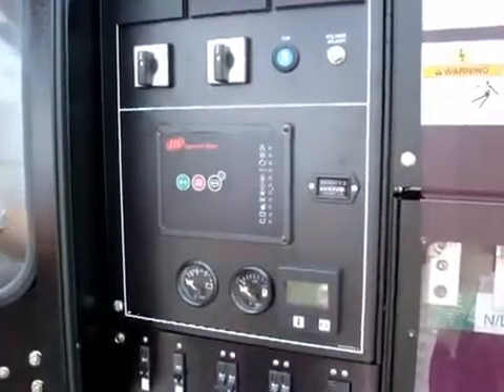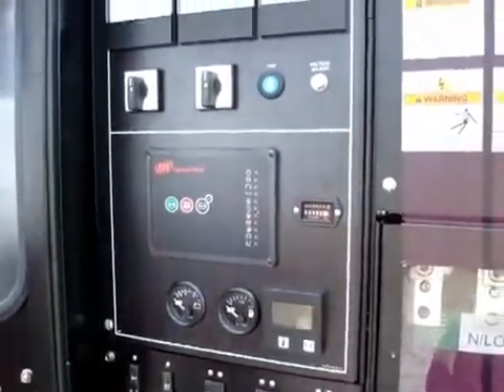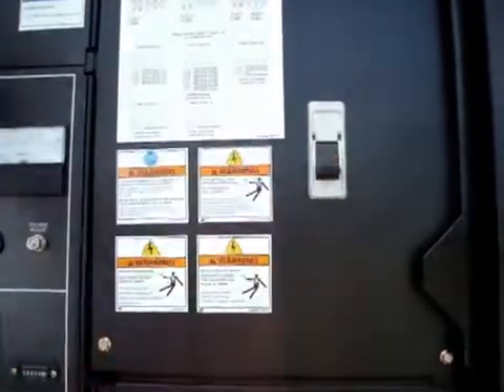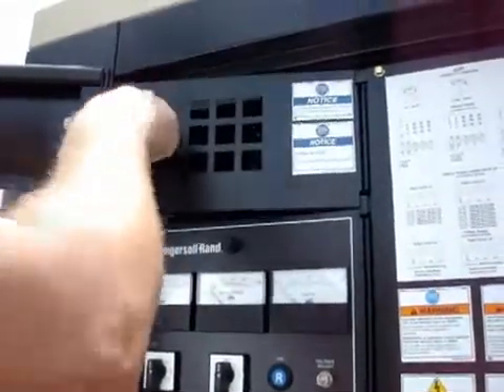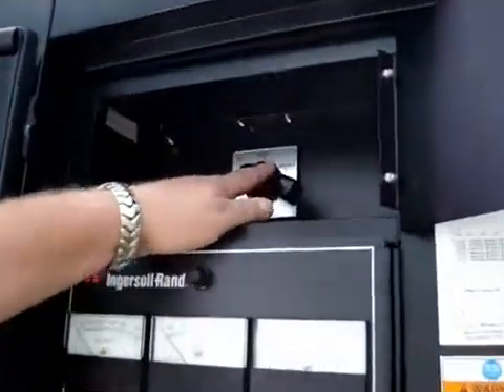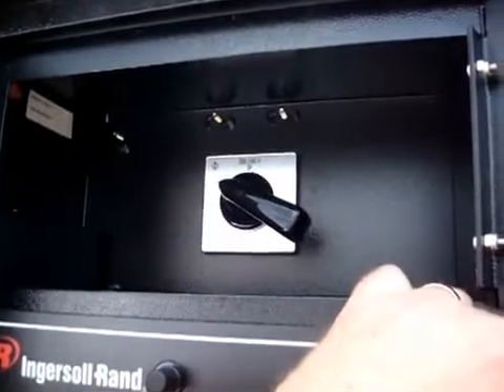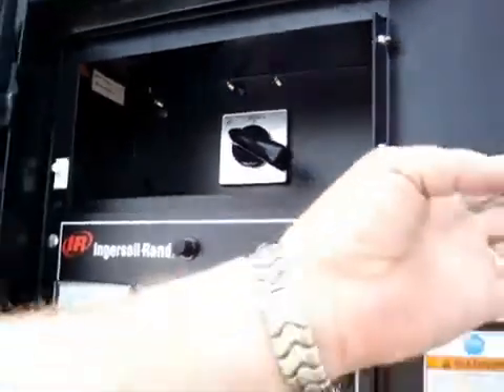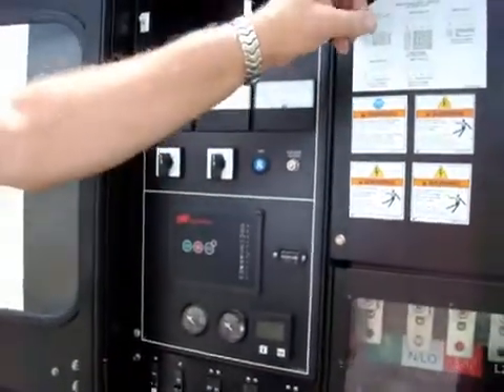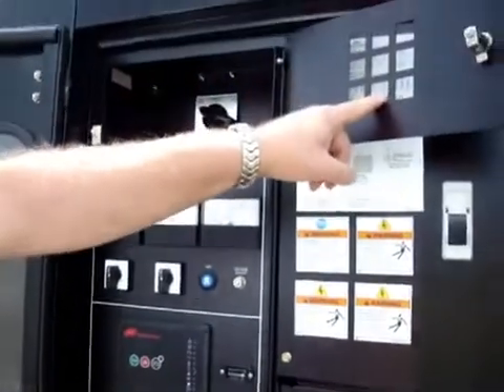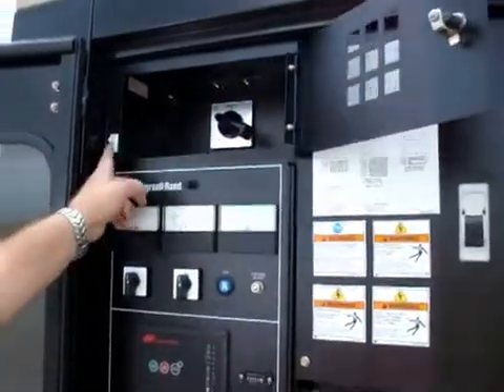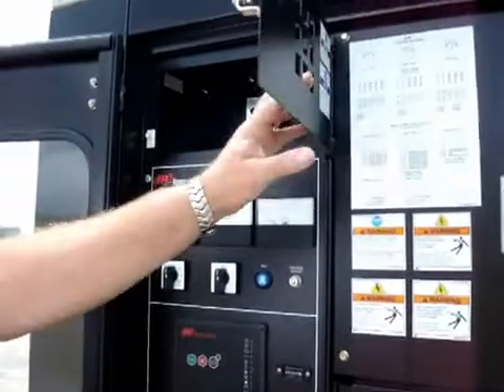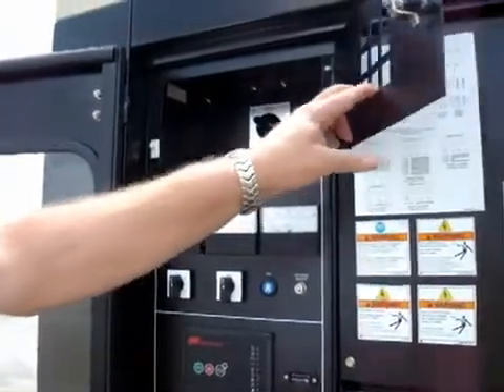Okay, basic controls prior to starting up. Once again, verify the breaker is open. We'll verify that our voltage selector switch is in the voltage that we desire. In this case, it's in the 480 volt three-phase position. We must verify that before we start the machine, this door is shut and latched due to the interlock that will shut the machine down should it come open during operation.